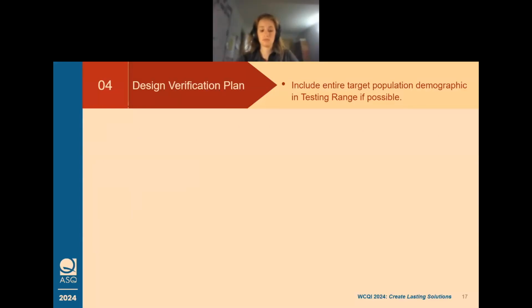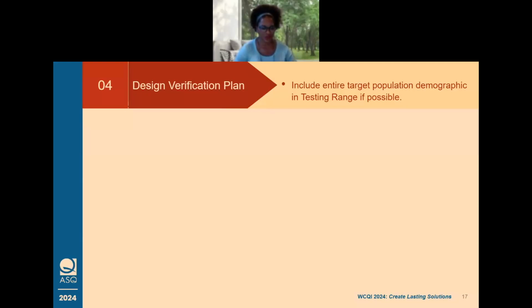All right, so let's talk about the design verification plan, because we've got a design input. Now we have our design output specification. So the design verification planning document provides an outline of the activities needed to provide evidence that the design input requirements have actually been met. This is achieved, of course, through objective evidence, through testing and inspection of the production builds that were manufactured according to the design output requirements, right? This also includes an analysis of the results to ensure that the product passes the verification testing.